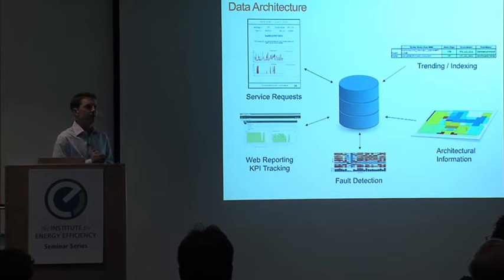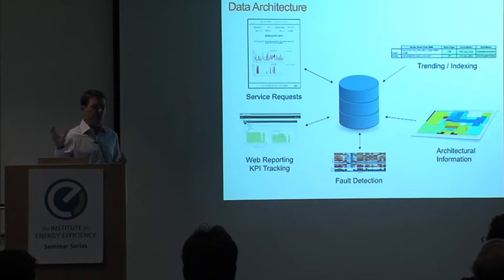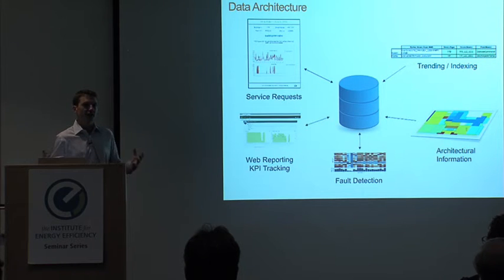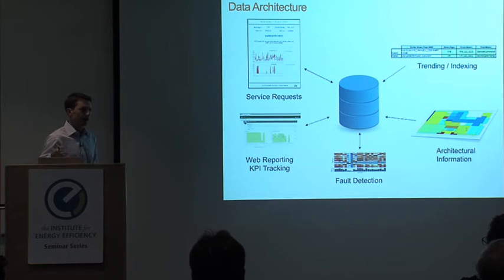So I think building analytics, and what's commonly referred to now as FDD—fault detection and diagnostics software—is where a lot of our focus is going. These software systems take all that information from your building automation system, sample all those 10,000 points every 5 minutes, and apply logic to determine whether everything in an air handling unit system—from the fan on the roof down to the terminal unit, the heating coils, and your thermostat—is functioning as it should for thermal comfort and energy efficiency. We've got EcoRhythm deployed at 4 buildings now, and we're looking to expand to more buildings on campus as we get past the initial onboarding workflow.